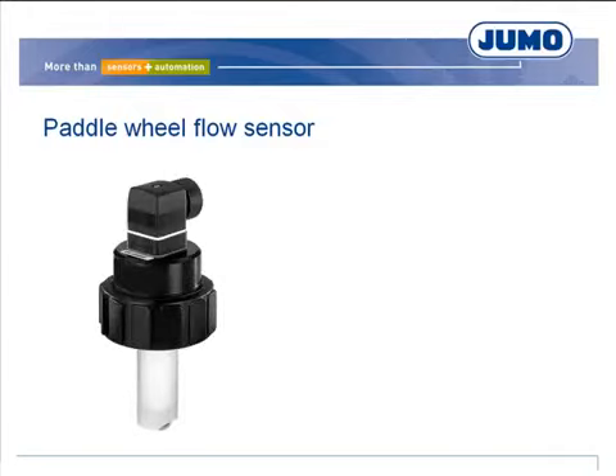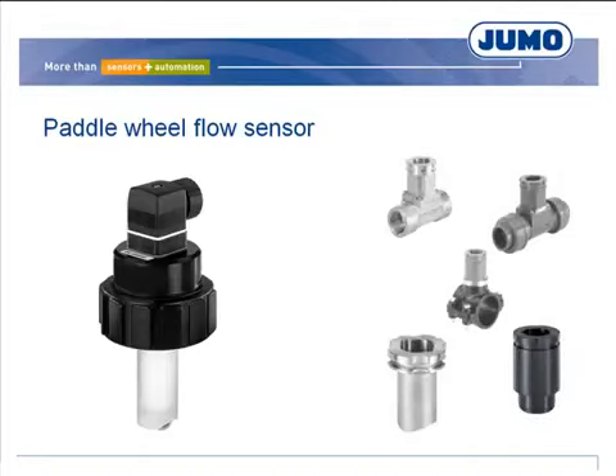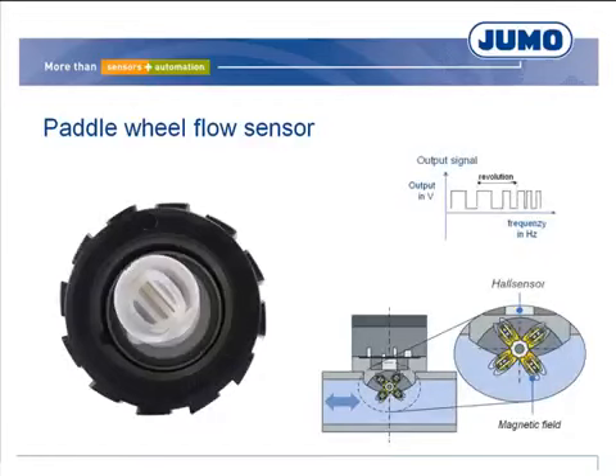The paddle wheel flow sensor is in the lower price segment and is suited for non-aggressive and low viscous liquids. It is supplied with special armatures, which are suitable for pipe diameters from DN15 to DN400. These are ordered in stainless steel or plastic, depending on the application. The paddle wheel sensor measures the flow mechanically and outputs a frequency which is proportional to the flow.